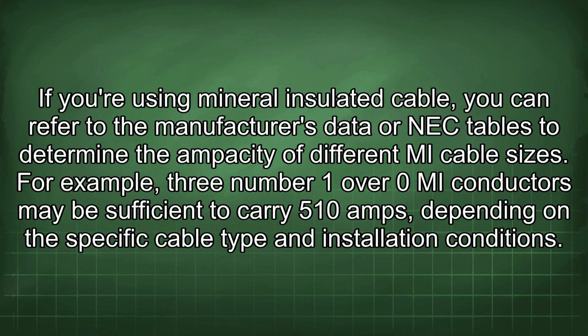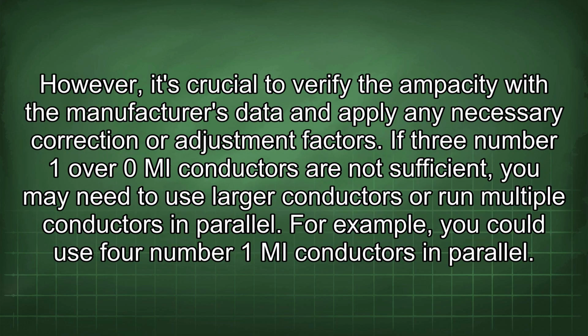If you're using mineral insulated cable, you can refer to the manufacturer's data or NEC tables to determine the ampacity of different MI cable sizes. For example, 3 number 1/0 MI conductors may be sufficient to carry 510 amps, depending on the specific cable type and installation conditions. However, it's crucial to verify the ampacity with the manufacturer's data and apply any necessary correction or adjustment factors. If 3 number 1/0 MI conductors are not sufficient, you may need to use larger conductors or run multiple conductors in parallel.